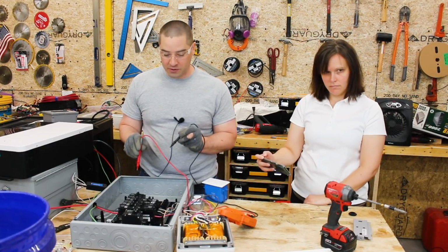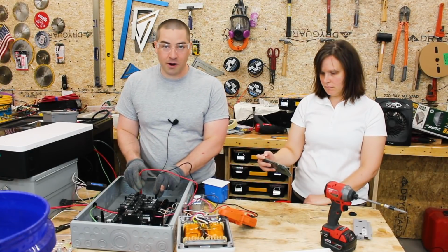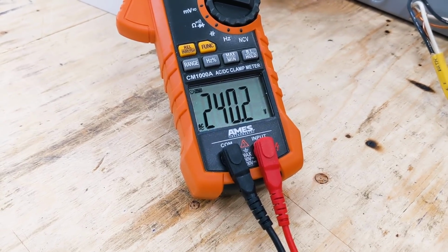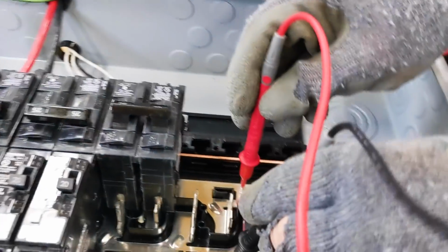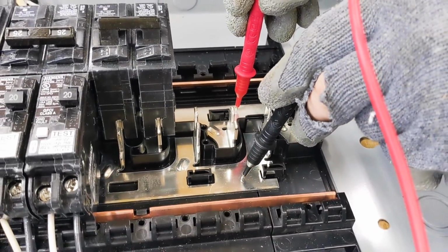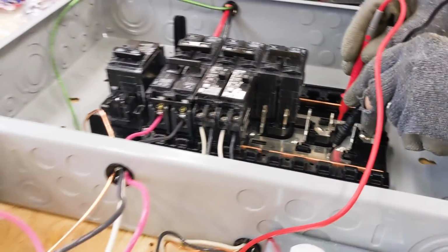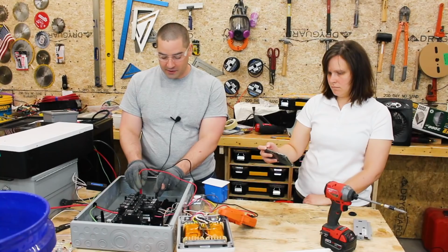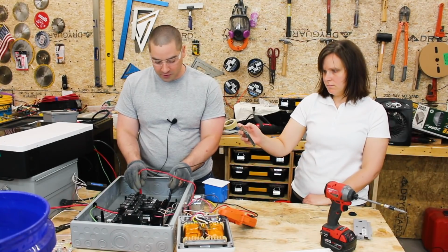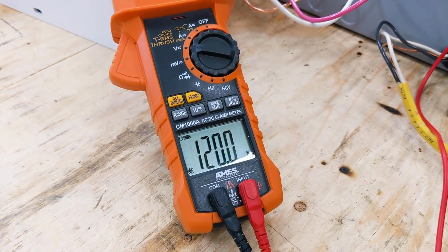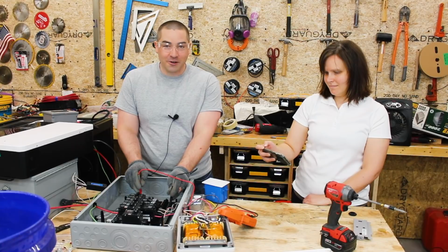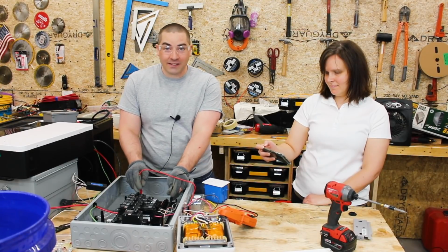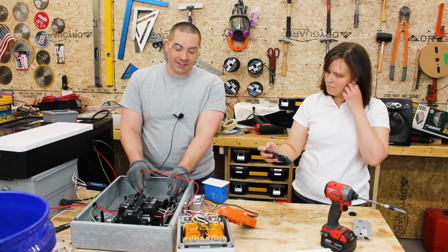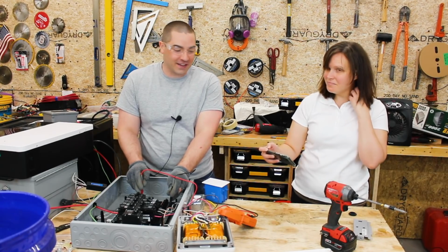So first thing we'll do is check the two big bus bars. And we have 240 volts. Can you see where I'm holding these? So 240 volts. Now what we'll do is check from one hot leg to the neutral. And it's 120 volts. That's it. We did it. We got a neutral. We split the single phase 240 into two 120 volt phases.